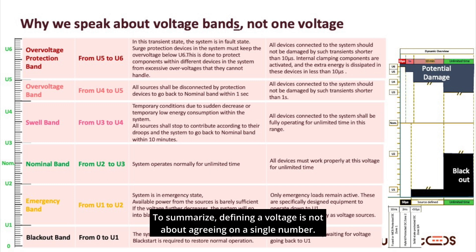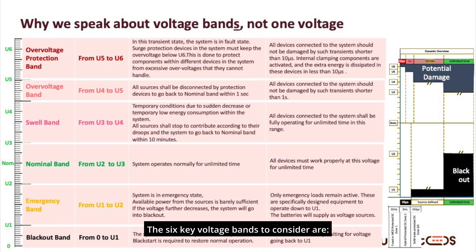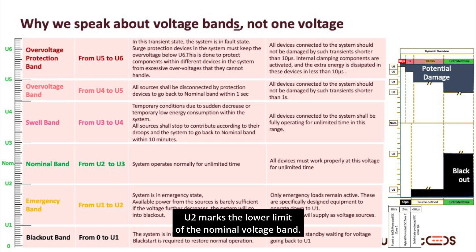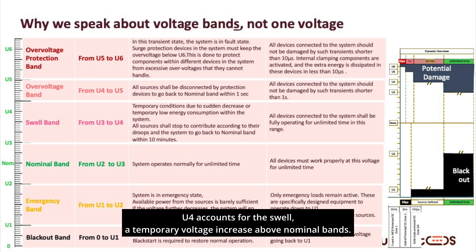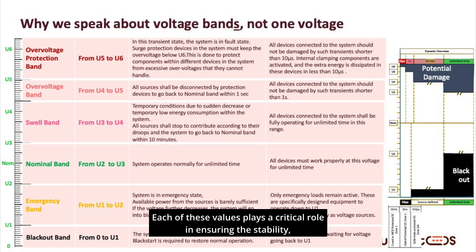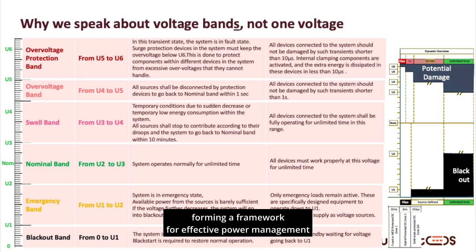To summarize, defining a voltage is not about agreeing on a single number — it's a spectrum of values that must be carefully defined, particularly when dealing with electronic protection systems. The six key voltage bands to consider are: U1, which represents the blackout state and the voltage required for a black start to energize the microgrid; U2, the lower limit of the nominal voltage band; U3, the upper limit of the nominal voltage band; U4, which accounts for the swell — a temporary voltage increase above nominal bands; and U5 and U6, which outline the range where clamping systems come into play to protect against transient overvoltages. Each of these values plays a critical role in ensuring the stability, safety, and efficiency of a DC microgrid, forming a framework for effective power management and protection.